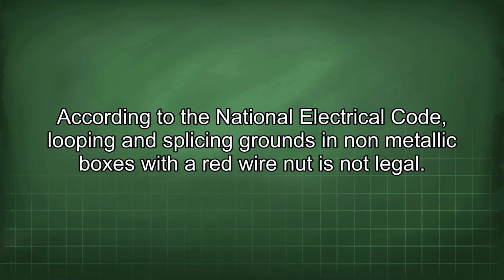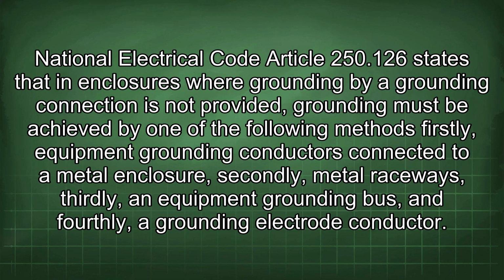According to the National Electrical Code, looping and splicing grounds in non-metallic boxes with a red wire nut is not legal. National Electrical Code Article 250.126 states that in enclosures where grounding by grounding connection is not provided, grounding must be achieved by one of the following methods. Firstly, equipment grounding conductors connected to a metal enclosure. Secondly, metal raceways. Thirdly, an equipment grounding bus. And fourthly, a grounding electrode conductor.